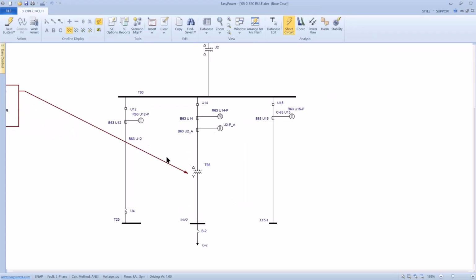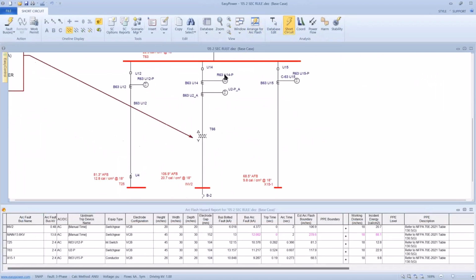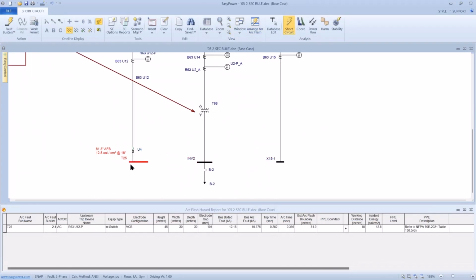When that's the case, the next thing I want to find is, is there any place where we have potential for miscoordination? Well, if we look at this, I'm going to fault the bus, look at incident energy. This is a 480 volt system. I guess I'd be better off looking at my range for arc flash. So here I have a 2.4K voltage and 12 calorie PPE, 12 calorie incident energy. On this bus, I have a 480 volt system, and it's tripping on manual time, which is the 2-second limit, and I'm still getting 20 calories incident energy. And likewise on this 2.4K. So my 2.4 kilovolt buses have more or less restrictive incident energy than my 480 volt. And yet I'm limiting everything to 2 seconds. So my question is, how's that coming about?